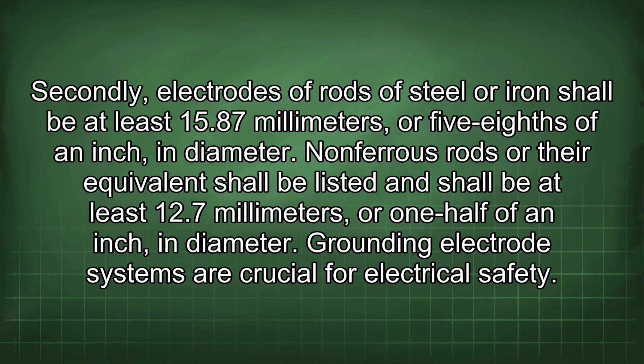Secondly, electrodes of rods of steel or iron shall be at least 15.87 millimeters, or 5/8 of an inch, in diameter. Non-ferrous rods or their equivalent shall be listed and shall be at least 12.7 millimeters, or 1/2 of an inch, in diameter. Grounding electrode systems are crucial for electrical safety.